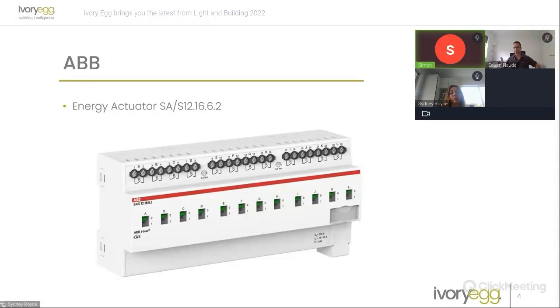This new generation of switch actuators is the latest generation, and every channel on that relay that you see, and they can come in 2, 4, 8 and 12 channel relays, every channel of that relay is a real meter. Okay, we can derive from each of those channels voltage, frequency, power factor, current, consumption, instantaneous. Okay, along with that, heavily focused towards energy monitoring and load shedding.